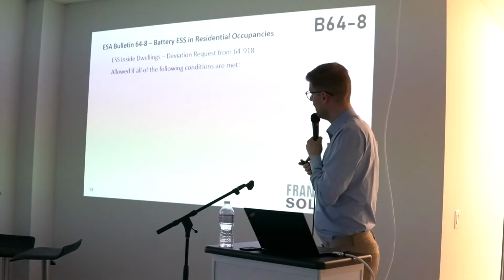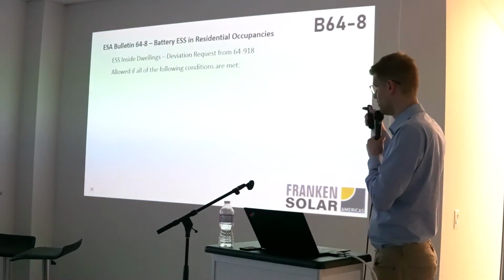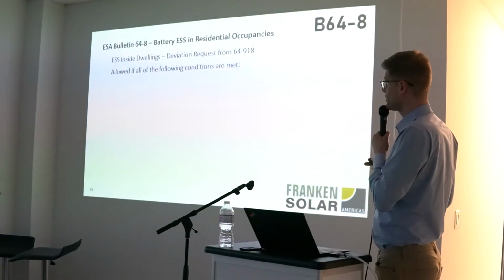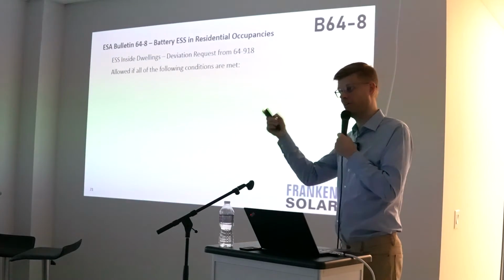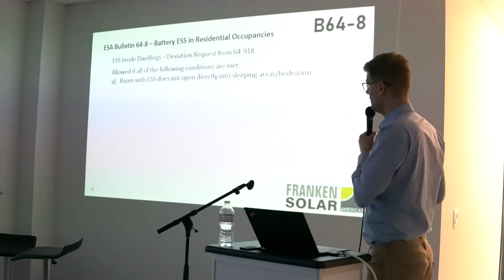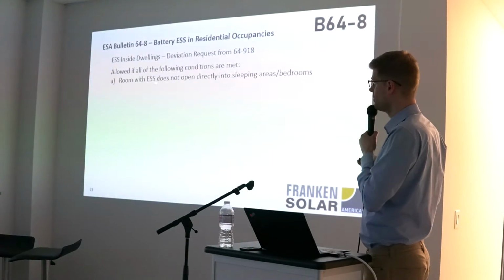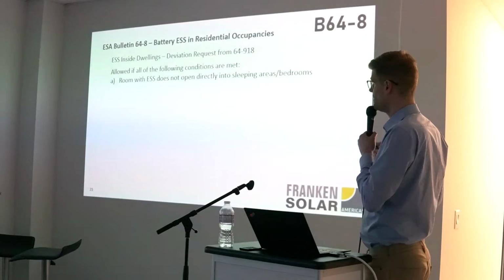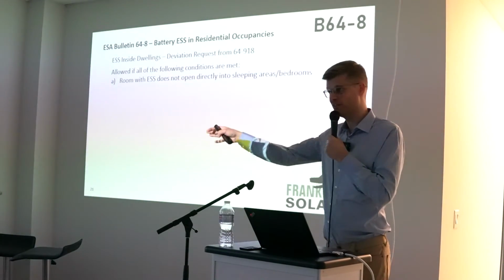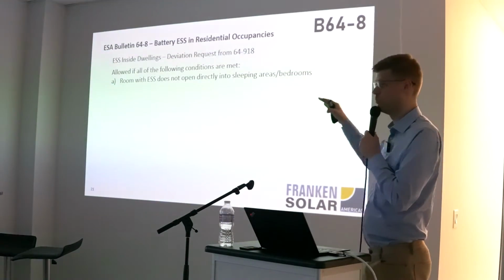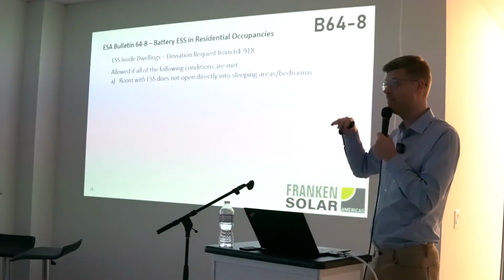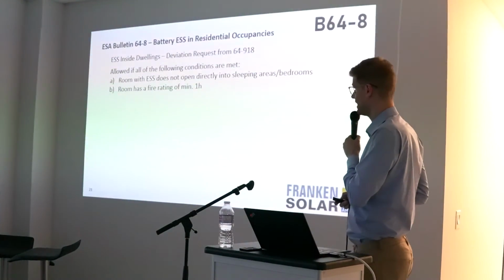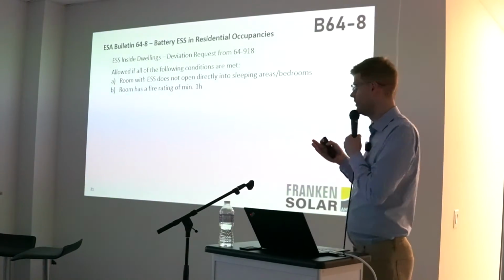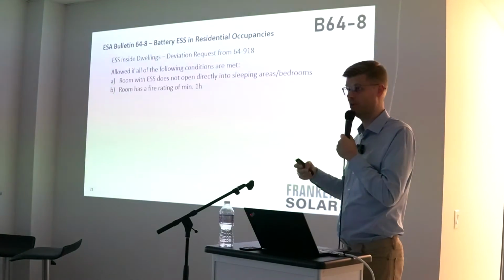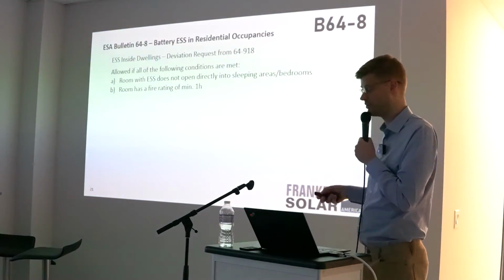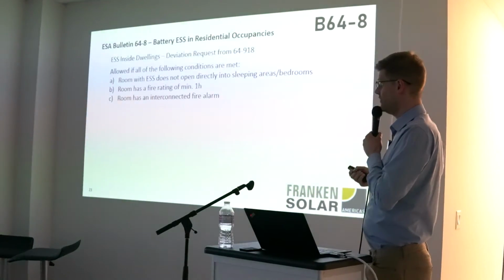All right, there is another option available, and that goes to a few of the other points I mentioned earlier. You can install inside dwellings, and that refers to the 1 kilowatt problem and the below grade problem. If the room you install the energy storage in does not open directly into a sleeping area or bedroom, so there's no door that directly exits or goes into a bedroom, then this room would be a suitable room to put that energy storage system even in your residential dwelling. Second, the room you're putting it in has to have a minimum fire rating of 1 hour, so you have to have your special drywall doubled up or whatever other structure. The room has to have an interconnected fire alarm.